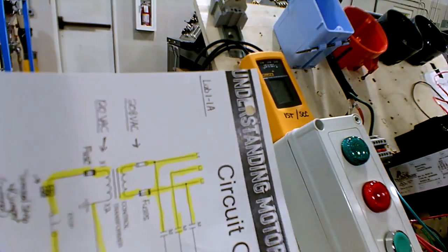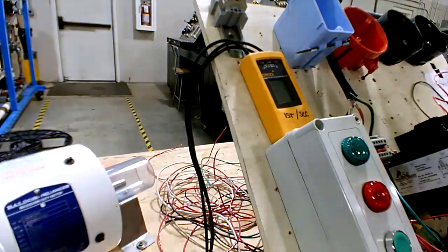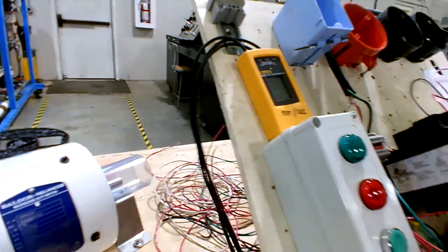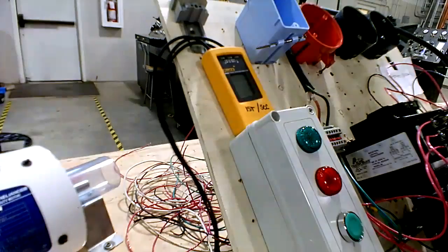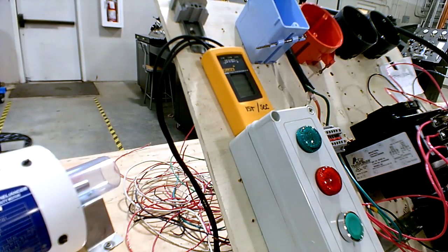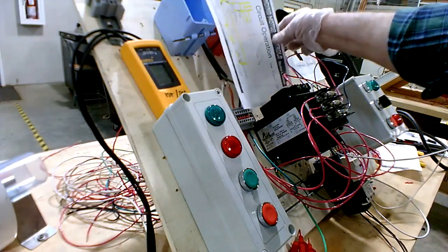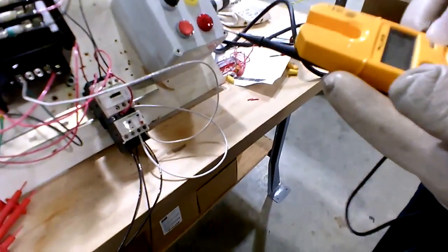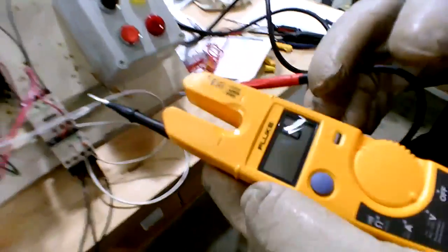So now you're going to get your meter out and go to the motor leads and check from each phase to ground, leaving the starter. And then check phase to phase, leg to leg, 1 to 2, 1 to 3, and 2 to 3, on the leads going to the motor. So you use a regular meter for that, just not that one. You go on volts. Be careful about the purple button. The purple button is a hold button. If you press it, it's going to freeze the reading on the screen and it won't update. Okay, so yeah, your phase to phase.